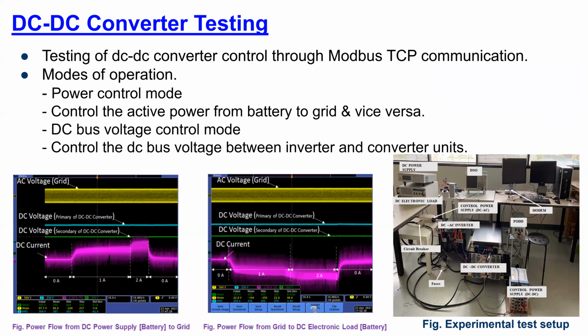If we use many battery packs, it's possible that some will have lower SOH than others. So ideally we need to connect a DC-DC converter between the battery and the inverter so we can control each battery pack independently, whether it's charging, discharging, or balancing. This way, the whole energy storage system can work consistently for the same amount of time, so you don't have to swap out battery packs in the middle of the application. This is very important.